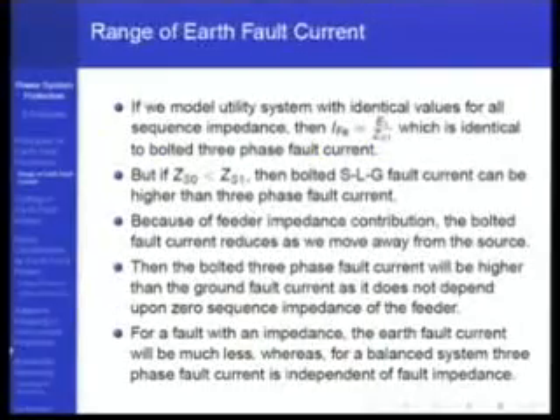So the point is that while we don't want fault currents to be abnormally high, something which we cannot handle and which damages the device, if the earth fault currents reduce too much also, we have a problem in coordination as well as detection. So the Zn is not just something you open circuit. Why ground the generator, don't ground it at all, you will get zero fault current.